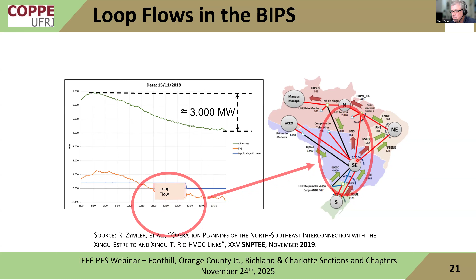And you see that the wind stopped blowing in the northeast. There was a decrease of 3 gigawatts in some hours. So the conventional generation in the southeast picked up, and then at 11 a.m. the AC reversed, as you can see here in these arrows going up. In this picture, the black arrow is the HVDC line, and green and red are AC lines. The DC was pushing power down and the AC was pushing up. But they had 1.5 hours to figure out that something was wrong, and then they shut down the DC line in order to get rid of this loop flow that was traveling 4,000 kilometers, or something like 2,500 miles, just creating losses in the system.